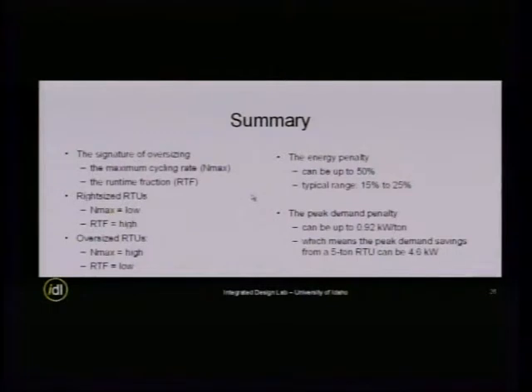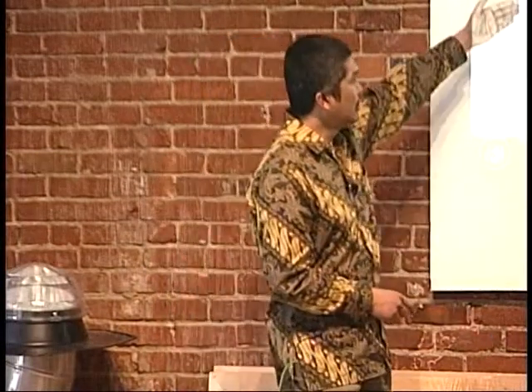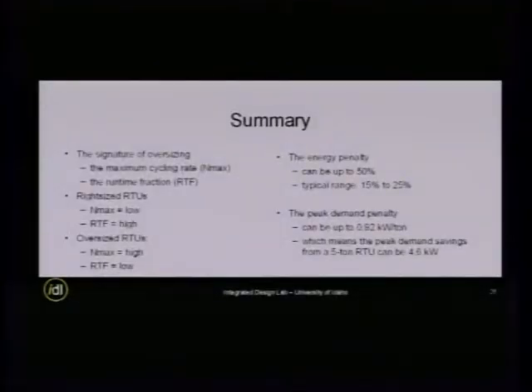So in summary, two parameters that we propose to be the signature of oversizing are the cycling rate and the runtime fraction. And as you can see, there are no fancy measurement instruments. It's just thermocouples or HOBO temperature sensors and current transformers. Clamp the wires on the compressor and the fan, record the cycling pattern, and you can come up with whether the RTU is oversized or not.